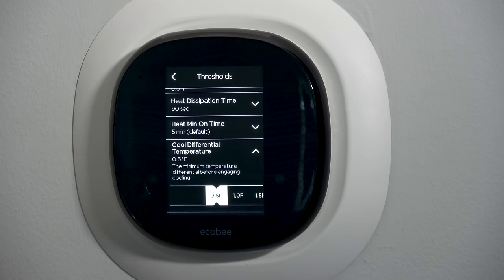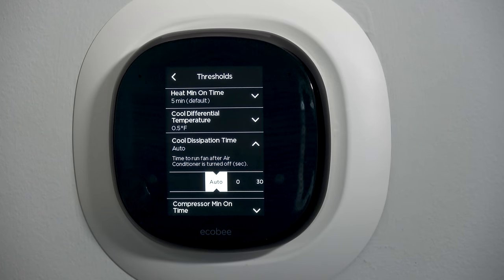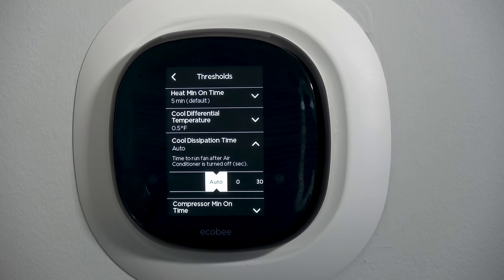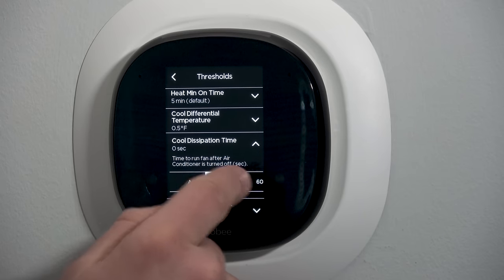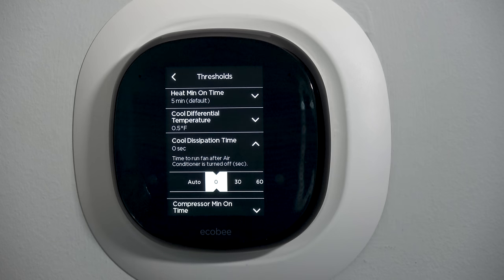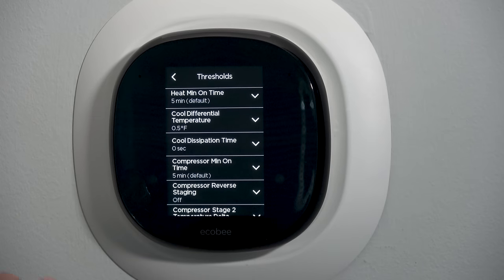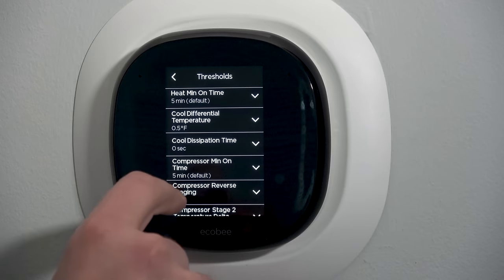Cooling differential temperature works just like the heating one — how many degrees do you wait before cooling engages? If you have a 75 degree cooling set point you wait till 75.5 to turn it on. I would use 0.5 or 1 and never go higher. Cool dissipation time: I recommend you turn this off and not use it. After a cooling cycle the evaporator coil is wet — if you continue to run the fan it will blow moisture off the coil back into the airstream, which defeats the purpose of dehumidification. Put the cooling dissipation time to zero. In the Midwest humidity situation, you don't want the fan running after a cooling call.